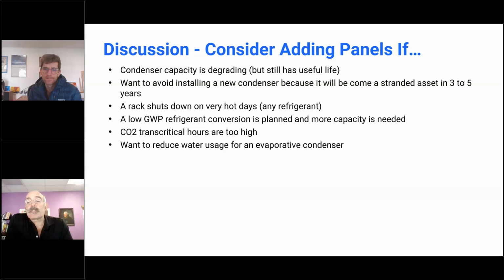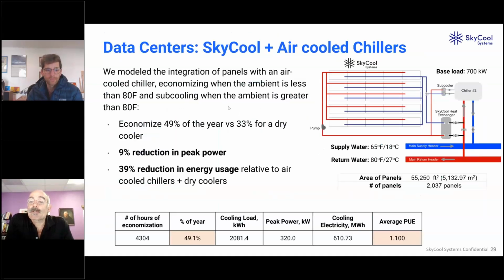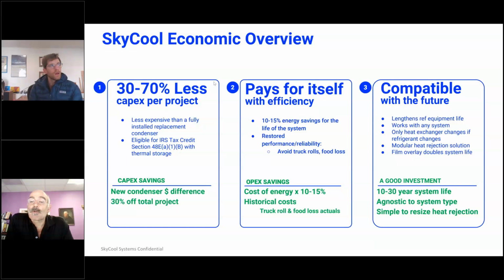Would the IRS tax credit, 48E A1B, apply to chillers, panels, and labor for a new system? So it would apply to the tanks and the panels. The language is essentially, and everyone should read this, and I can share a link afterwards, the equipment associated with cooling the tanks. And so our panels would cool the tanks, and the tanks would then provide the thermal storage capacity for the site.